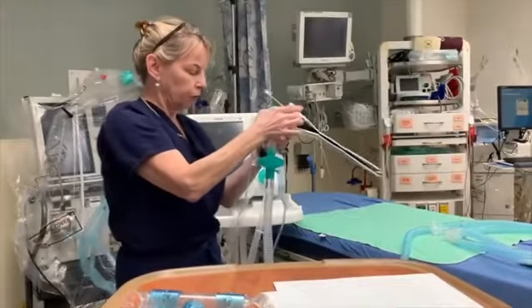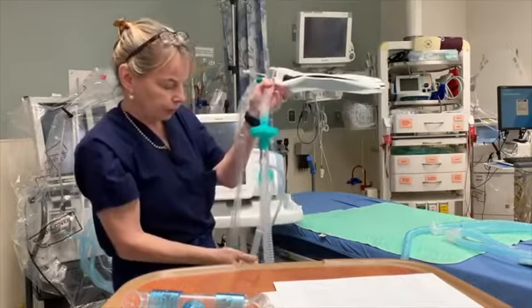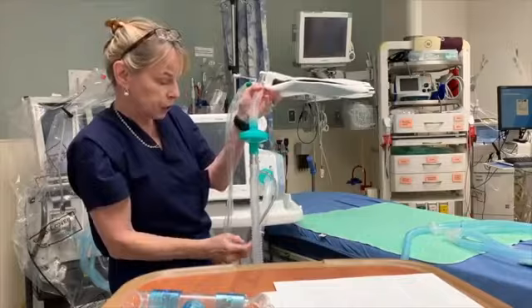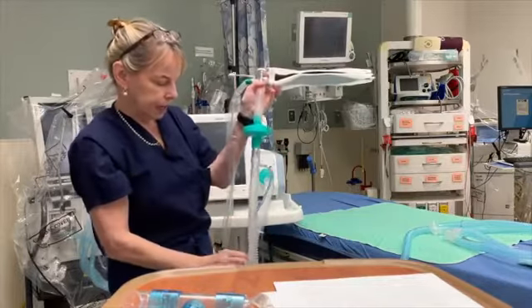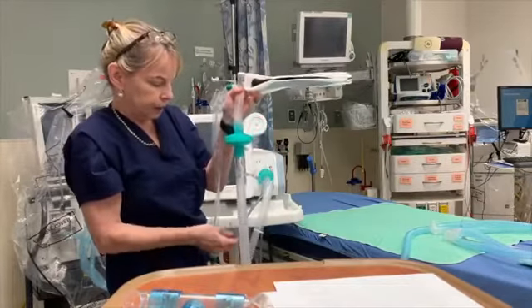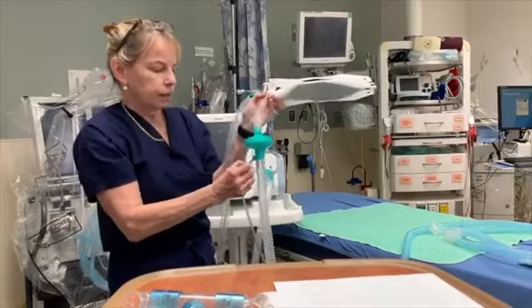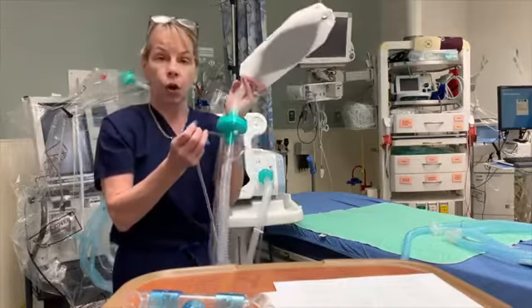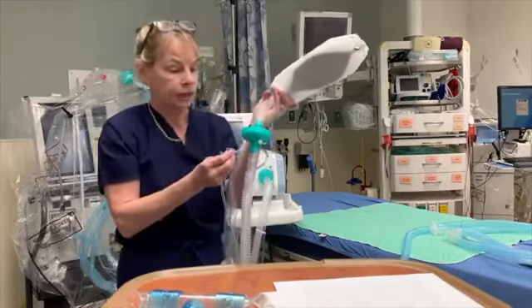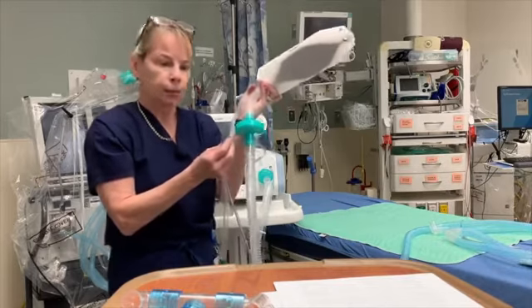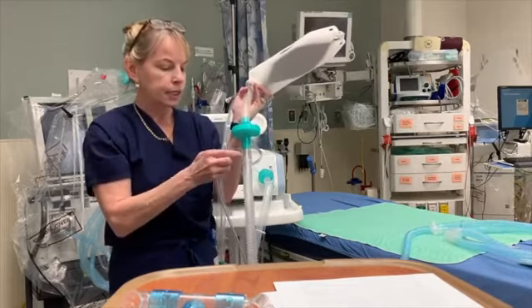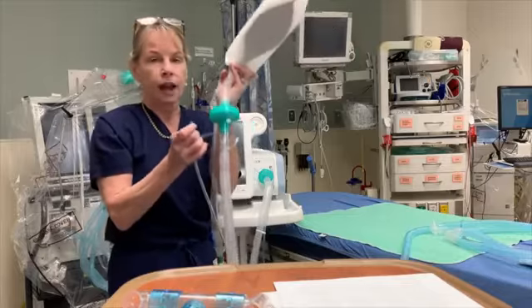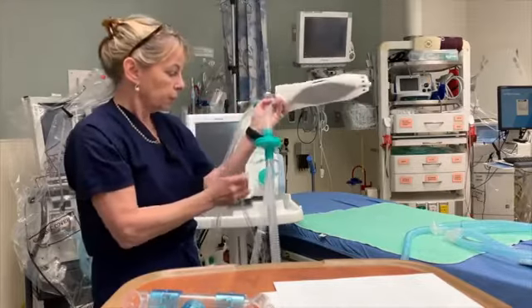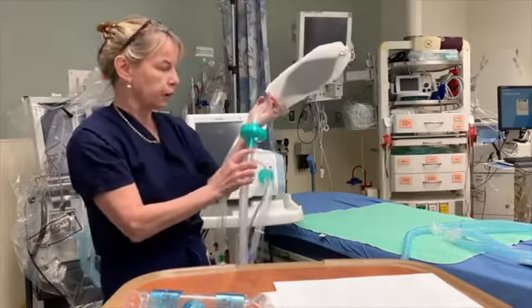Now, some of the tubing also comes with this little rubber stopper that can sometimes be used to put in place of that tubing and block it. Now, I would suggest that you cut this off so a nurse or somebody doesn't come along and say, oh, there's an air leak here, and put this in the port and block the port. That is the only expiration site for the patient. So cut that off. I left it on so I could show you, but that's the only expiration port.